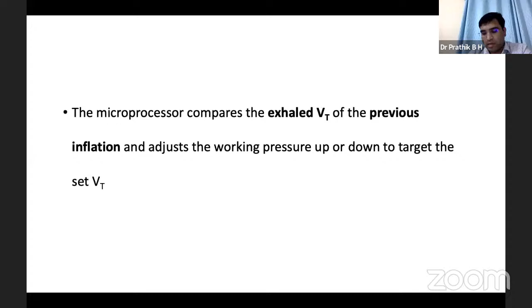Let us better understand with this graph. Here you can see in test breath 1, the ventilator will deliver a certain amount of pressure, that is, peak inspiratory pressure, and it notices the amount of tidal volume. In breath number 2, since the tidal volume target is not reached, the ventilator increases the pressure and again tries to achieve the target tidal volume.